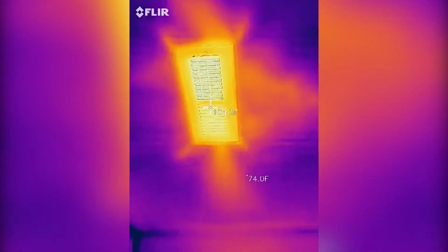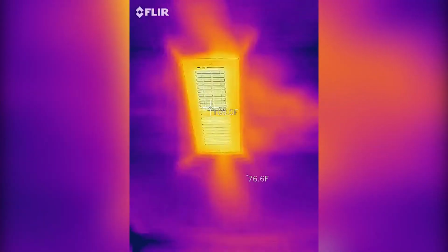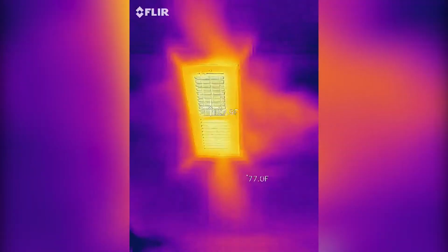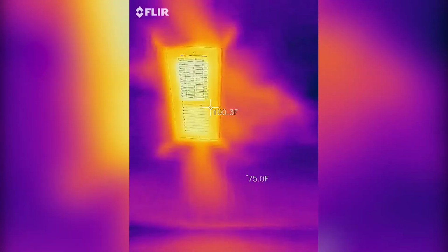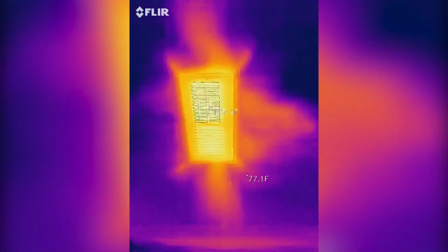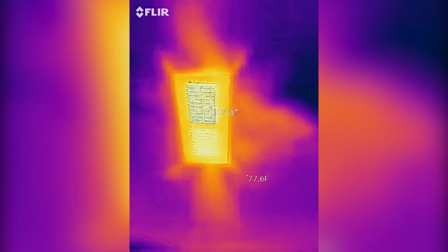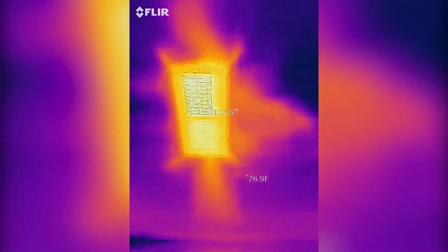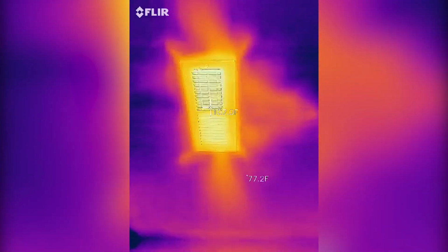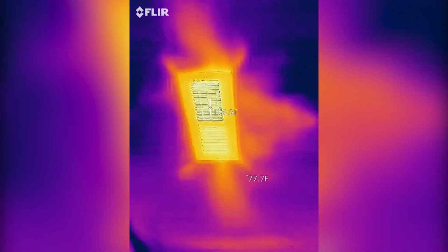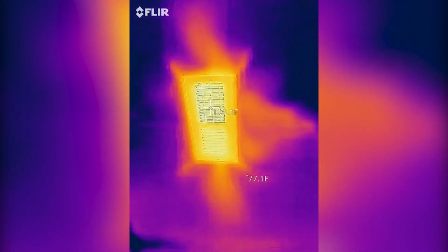All right, so here we're looking at the duct where it's coming out from the furnace. So it's already gone through the return, it's been heated, it's coming back out. You can see where the heat is blowing out everywhere across the ceiling. And right now we're getting a temperature out of this duct at about 107 to 108 degrees Fahrenheit. So we have a good almost 40-degree temperature differential between the air going in and the air going out. And that shows us that our heating and air conditioning system is currently working the way that it's supposed to.